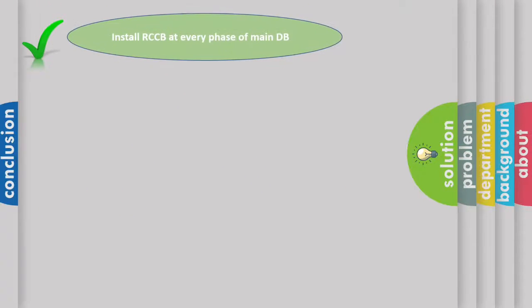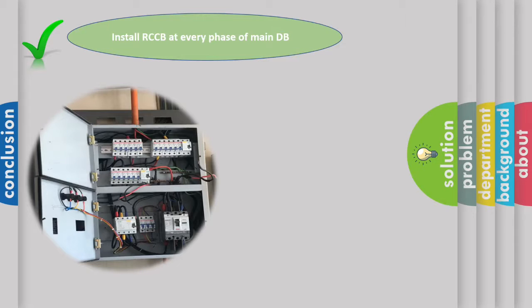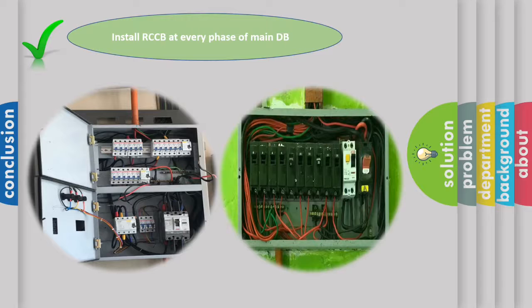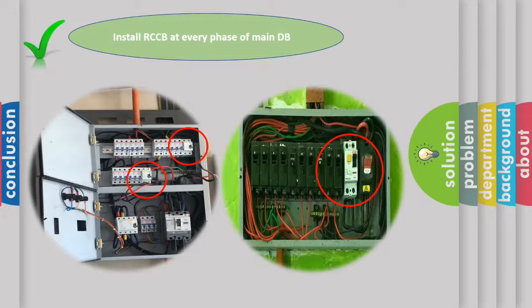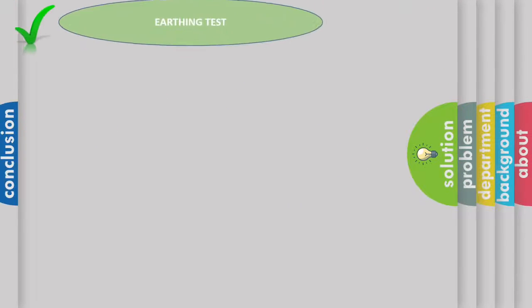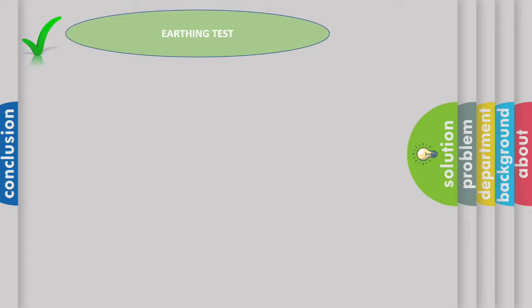The best solution is install RCCB at every phase. So, if any trip occur, it easily can be detected the tripping cause at one phase instead it affect all phase. Earthing was tested after install RCCB.